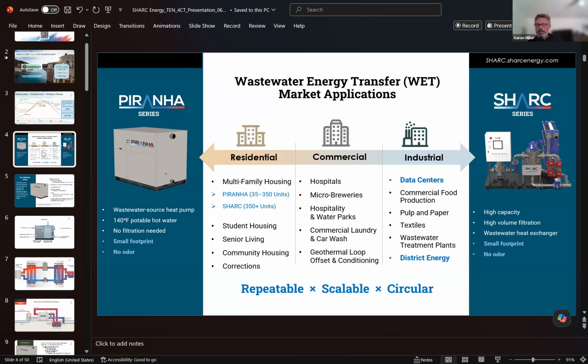So our small, and I put 35 down there, I'll be honest with you, 50 units is usually definitely enough people in it to make it work. I have a 37 unit apartment building in Boulder, Colorado operating right now, but it's a special situation. It's kind of like Boulder, Colorado's Silicon Valley. So if you want to develop there, you have to be completely passive house net zero ready. So this building has vertical, horizontal solar, every single bell and whistle you could think of. And they have a mandate for fully electrified hot water production, which is why it works well in that building. I'm not going to tell you that that same building in the middle of Hartford is going to pencil, right? So it's a case by case basis. The bigger the building, the easier it is for it to pay back, because again, you're getting that trade-off.